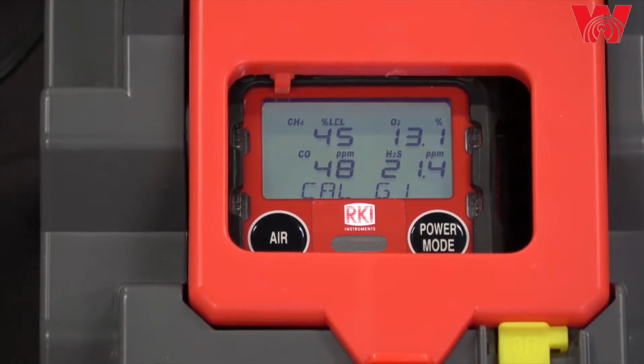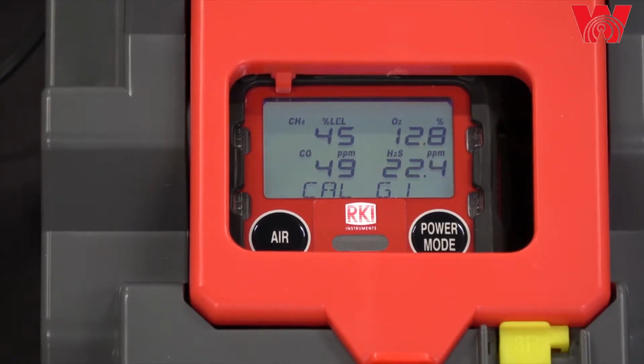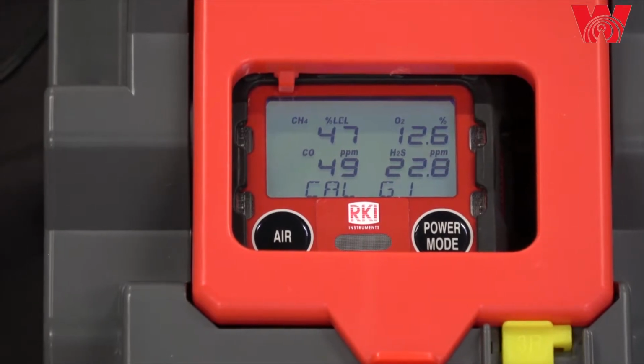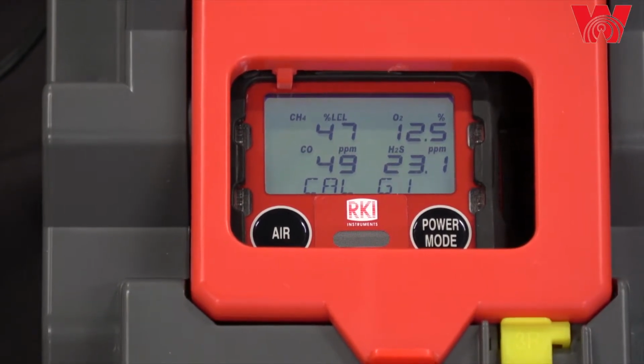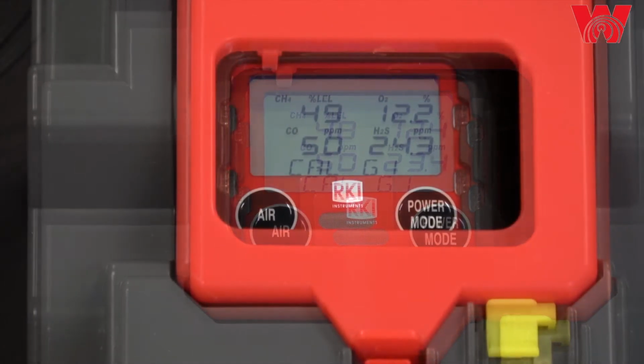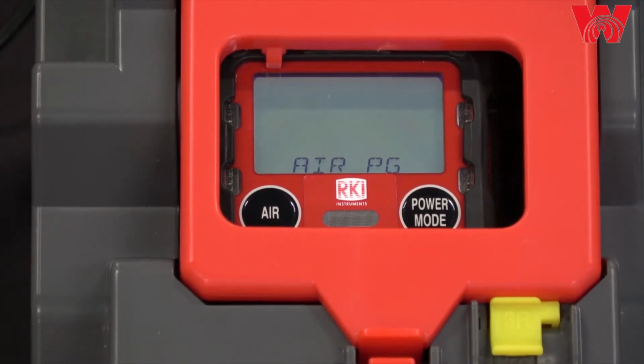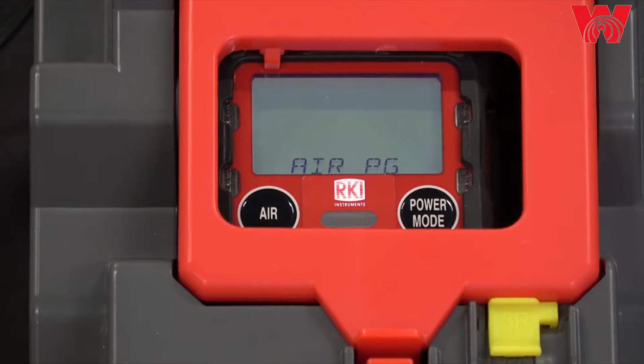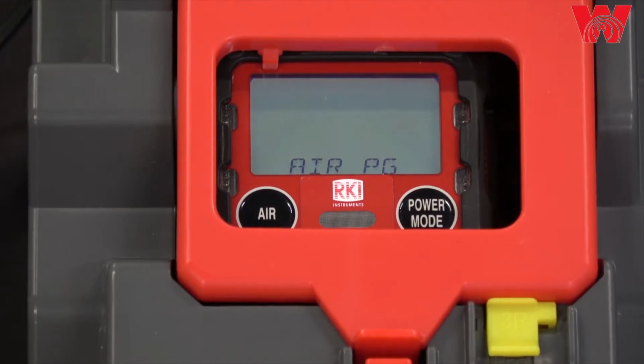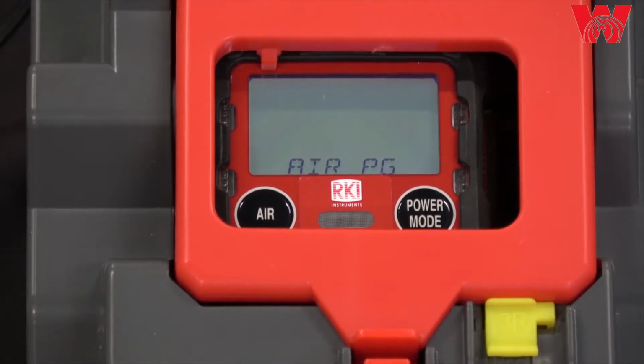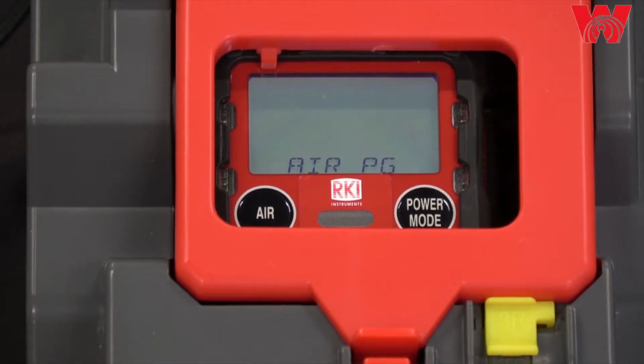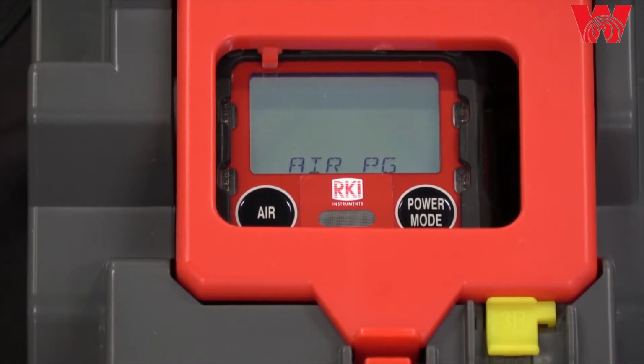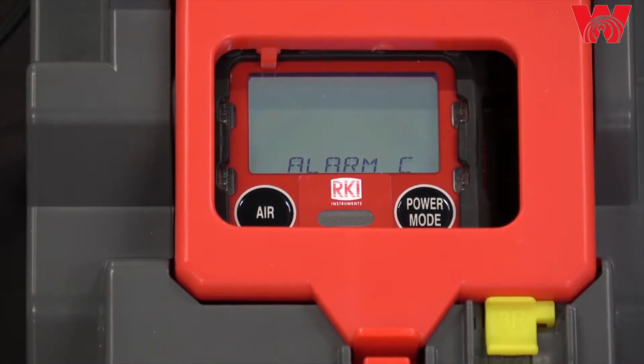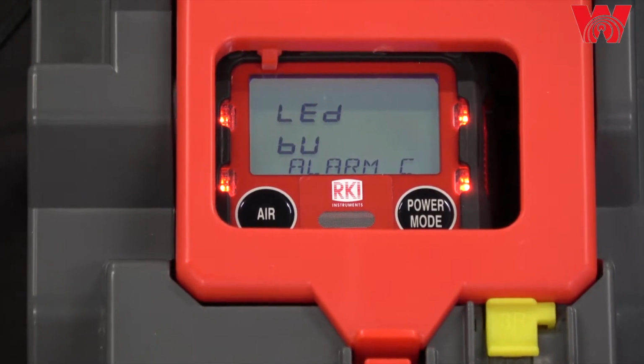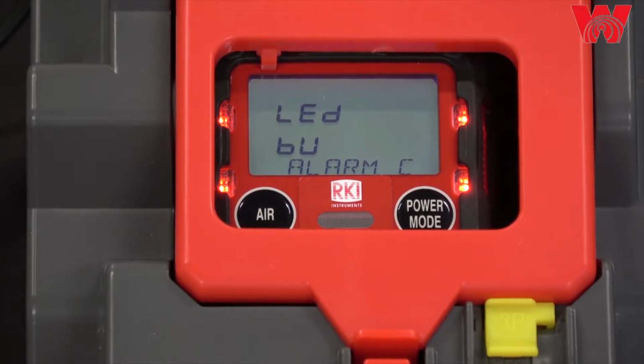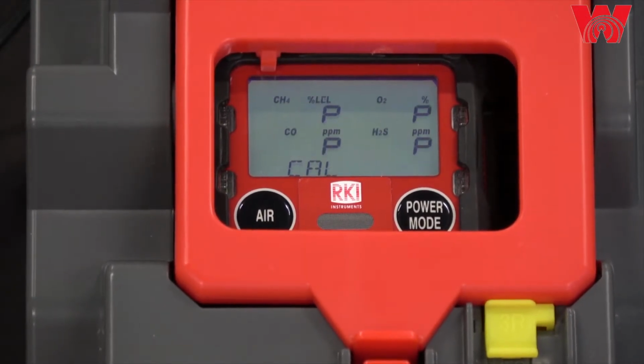The length of a calibration is adjustable in the Edit menu. And now it's flushing with air, just to make sure all of the calibration gas is out of the internal tubing of the SDM-3R. Now it's doing an alarm check. That checks LED and buzzer functionality.